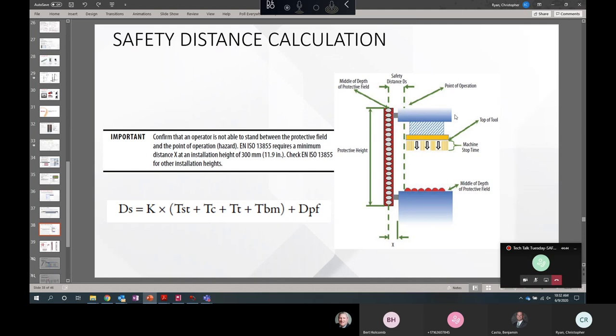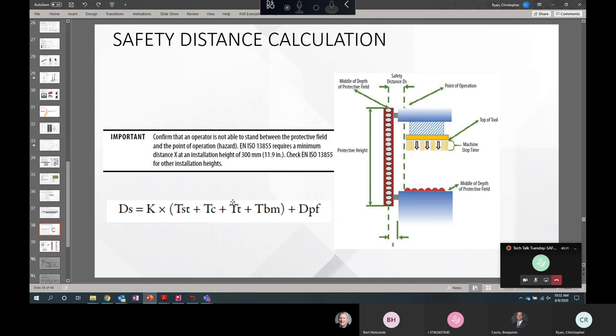And I just wanted to include this as a reminder to everybody as your functional safety technician for machinery that all presence and safety devices require you to use a safety distance calculation from your hazard. So in the United States, we use the ANSI standard, the B11.19 standard, which just says that your safety distance is equal to your hand speed constant. That's 63 inches per second. And you multiply that by the sum of your stop time of your machine tool, plus your stop time of your control system, plus your response time of your presence sensing equipment, plus your response time of your brake monitor. And then you add that to your depth penetration factor. And that depends on your resolution of your light curtain.